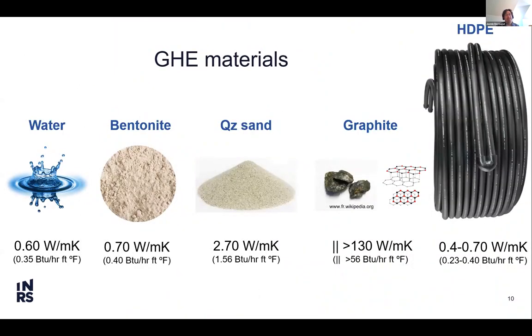The grout is actually made of a mix of water, bentonite, and sand. The idea of using bentonite is that when mixed with water, it inflates, and it's a low hydraulic conductivity material that prevents flow, but it also has a very low thermal conductivity, just 0.7 watt per meter Kelvin. So in the mix, we add quartz sand, which has a high thermal conductivity and can help improve heat transfer. But you need to balance it, not to have too much sand, right?